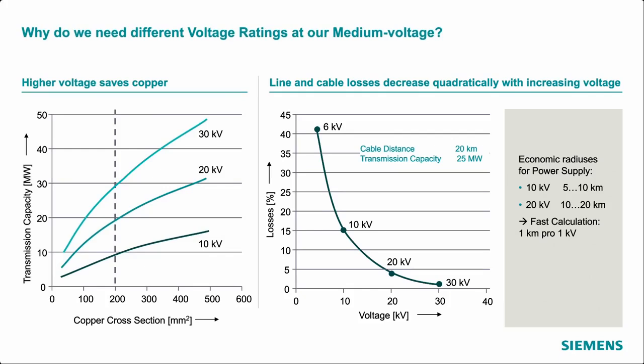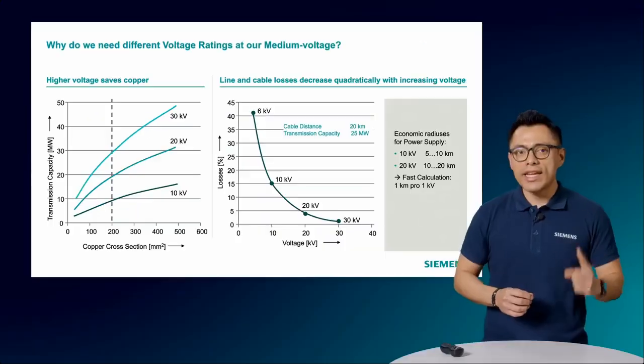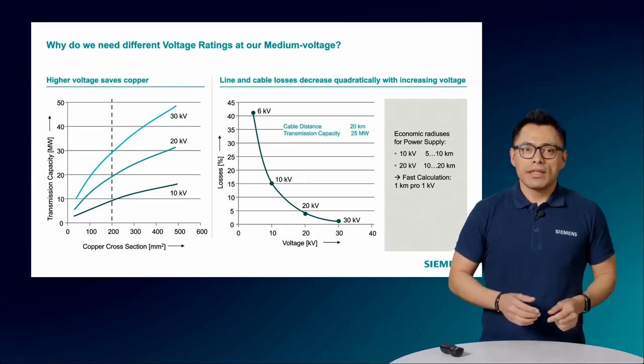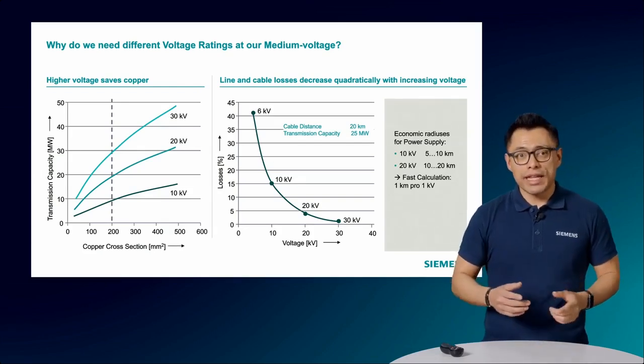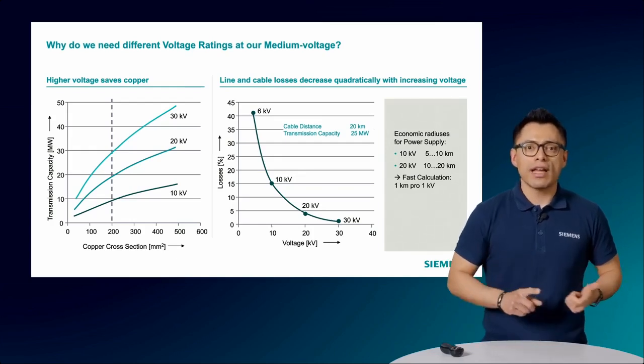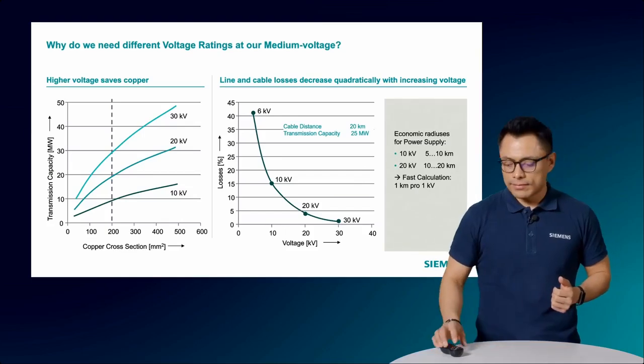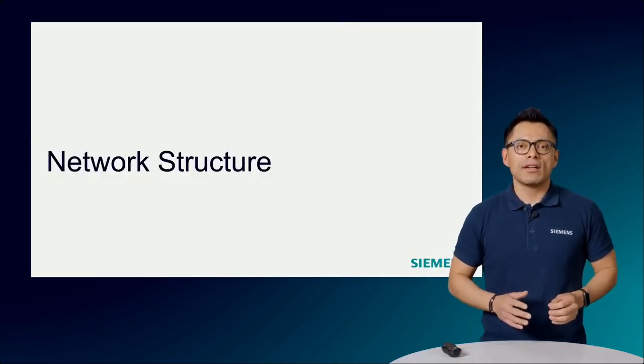Let's imagine we have a cable distance of 20 kilometers and we need to carry 25 megawatts over it. In principle, we can use whatever voltage rating we want. Nevertheless, please observe that the lower the voltage, the more losses we have. For example, at 6 kilovolts, we have more than 40% of losses, while at 30 kilovolts, we reduce these losses to nearly 2%. This is efficiency. As a rule, we can say that we need to increase 1 kilovolt per kilometer. In this way, by using different voltage ratings, we can ensure that power distribution is efficient, cost-effective, safe, and reliable.